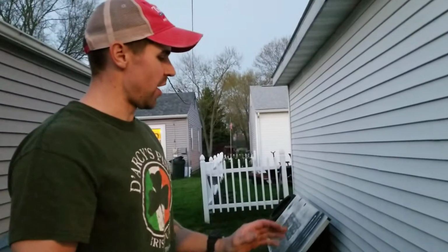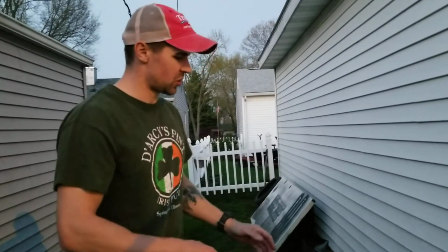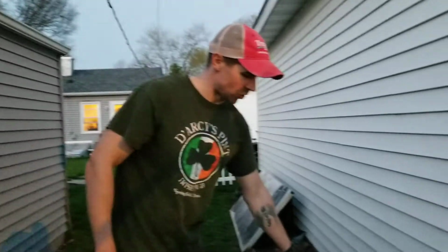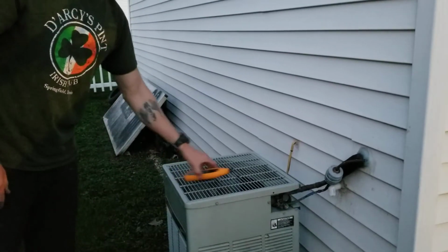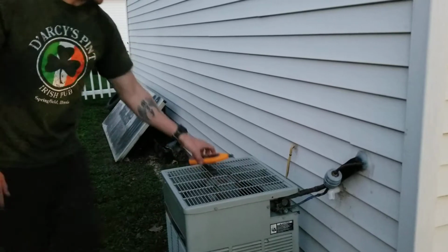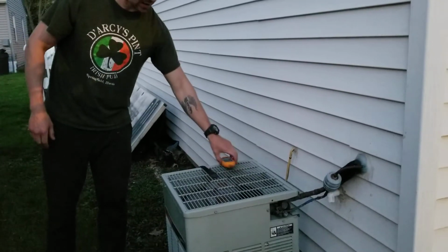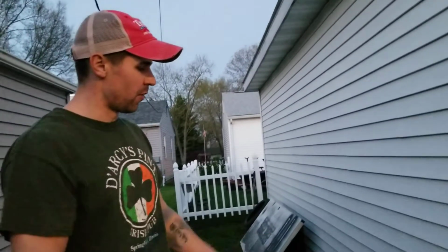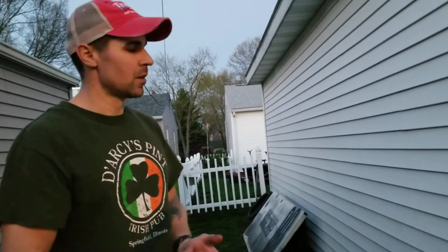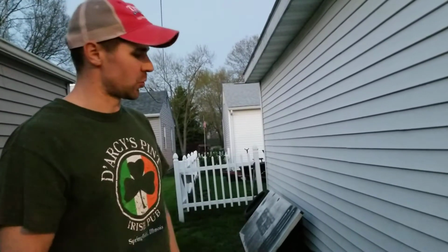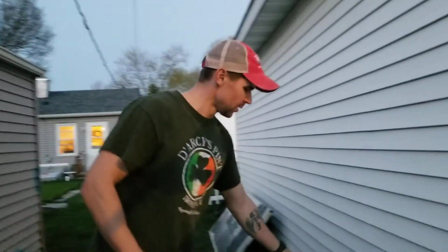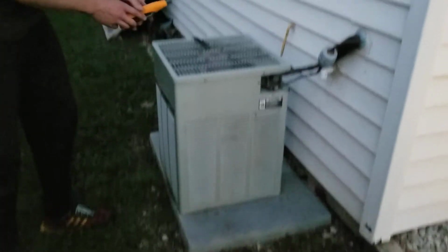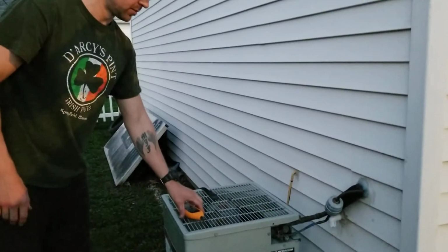When I say average air, you want to take multiple measurements depending on where your thermometer is. The temperatures could be different. So you're going to measure it here, write down what you got, measure it here, write down what you got, here, what you got. And then as we take an average, we add all those up and divide it by the number of measurements taken, we'll get an average. I've already done all these numbers because we're running out of daylight. But again, we take our entering air into the condenser, our average leaving air of the condenser.